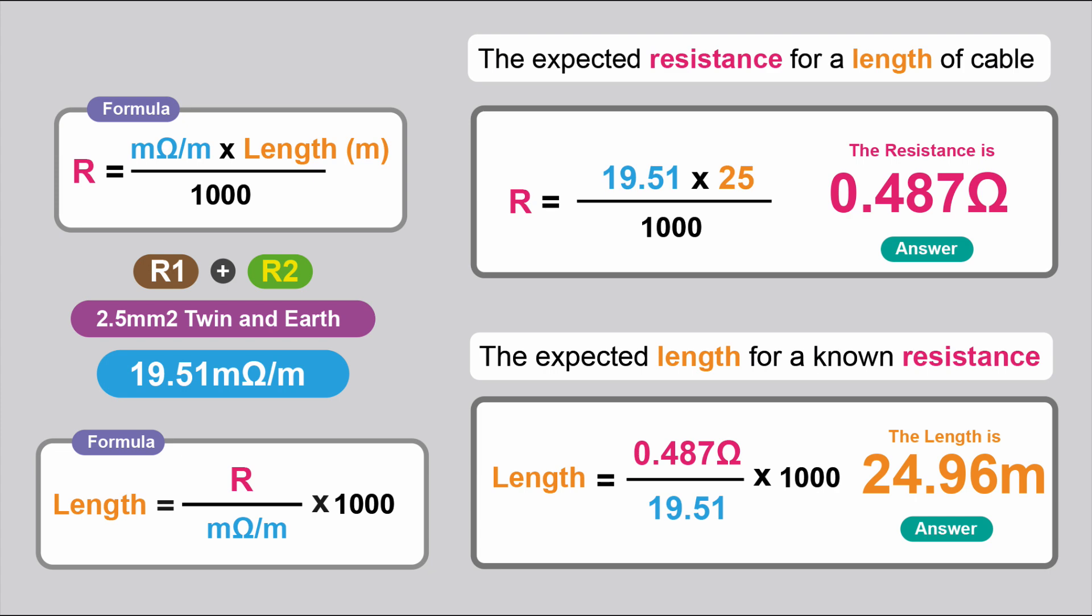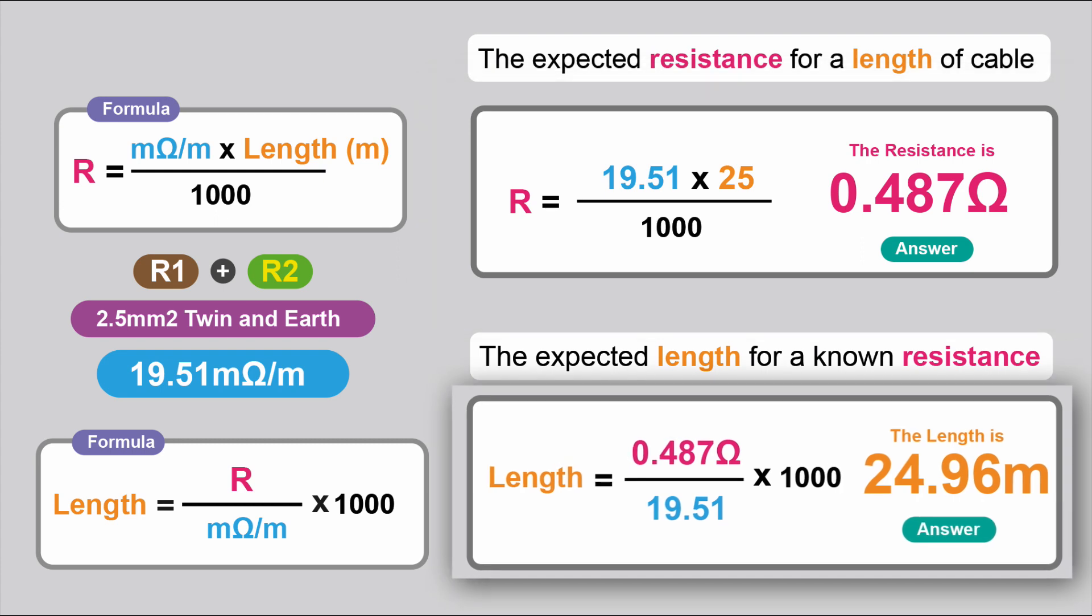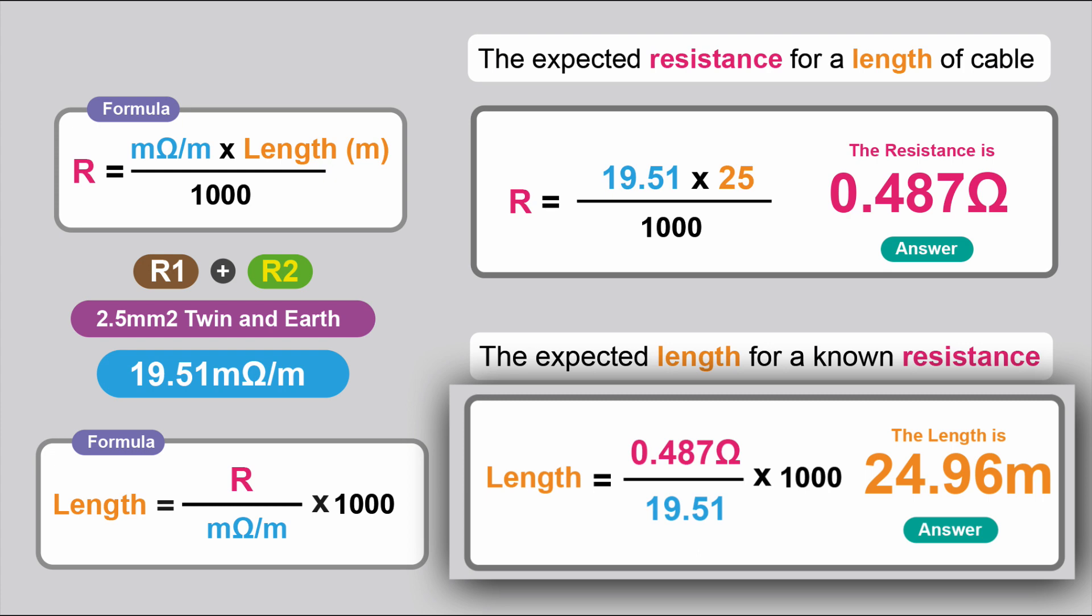We transpose it, so the length we're looking for now. So if we've got a resistance of 0.48 ohms, for example, what we do, we divide the 0.48 by 19.51, the milliohms per metre, and we times that by 1,000. That gives us 24.96 metres.